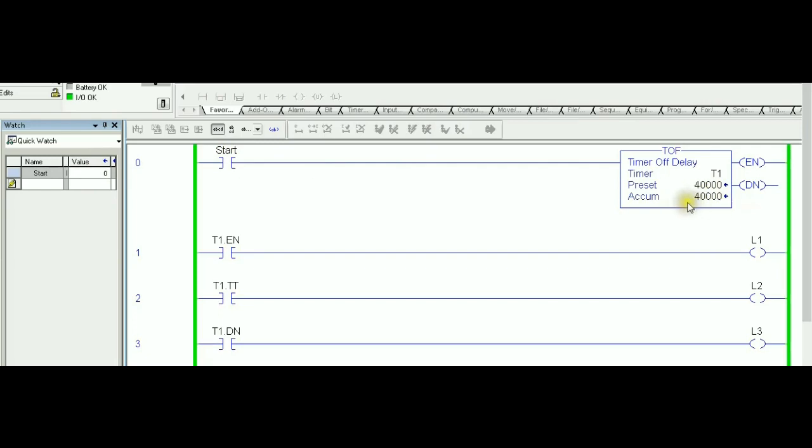As you can see, the first point: once you put the PLC into run mode, automatically the rung is still broken. There is no logic continuity across the rung. The accumulator starts with a value equal to the preset value, so that's opposite to TON.